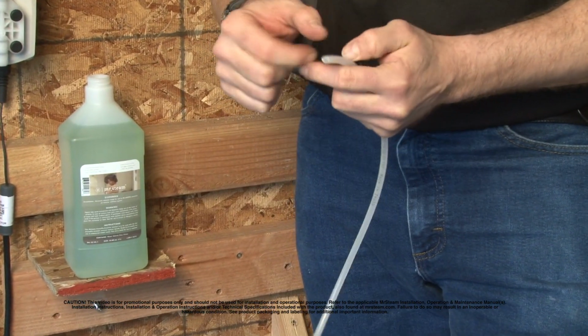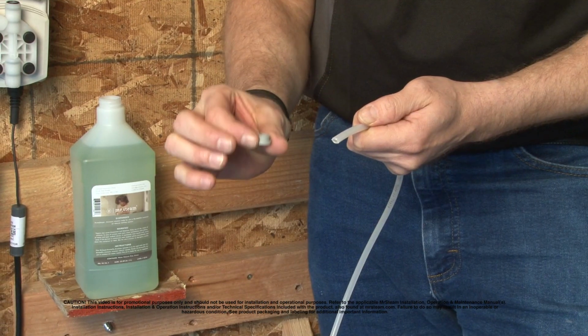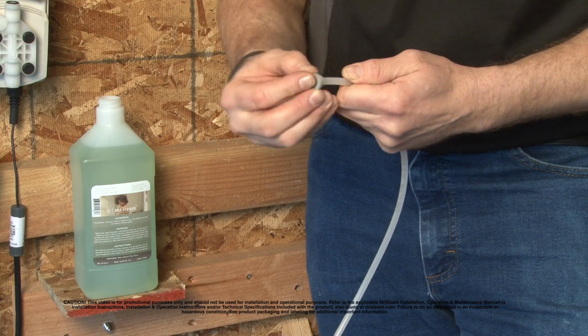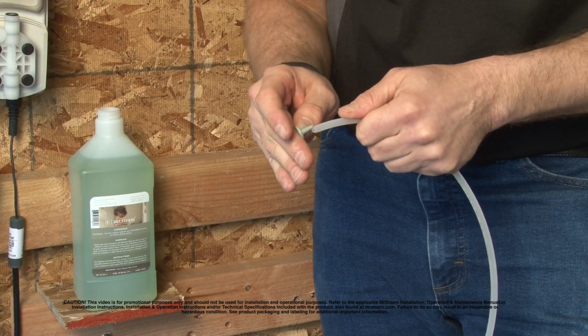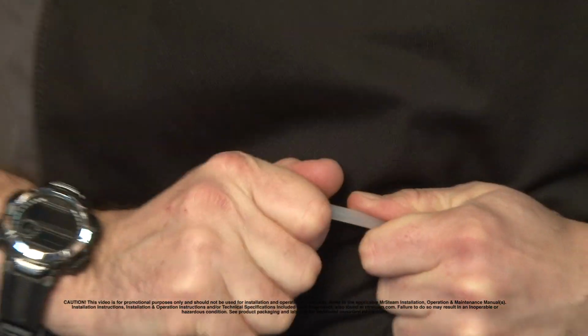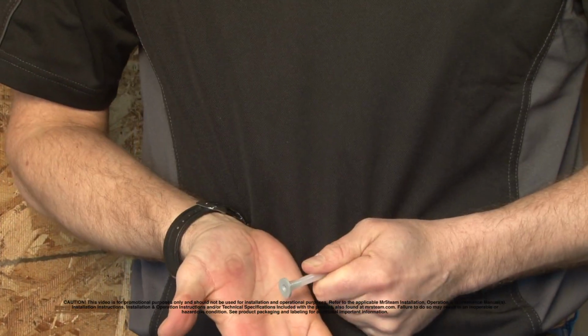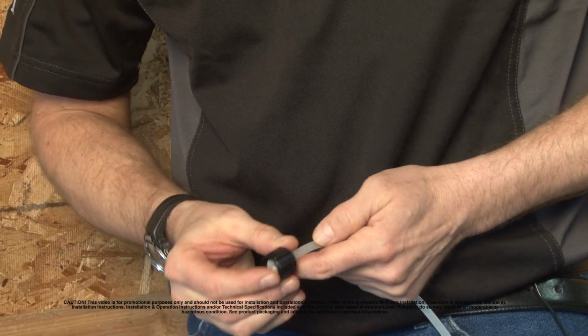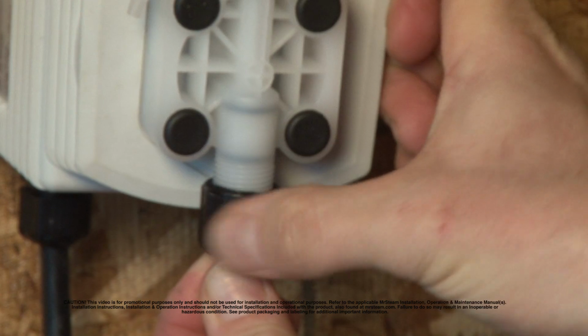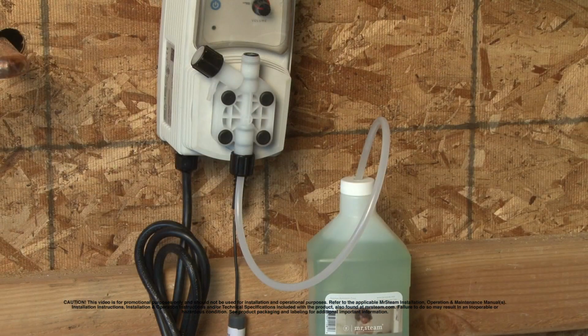Next, the other end of the hose should be threaded through this tightening nut and collar, and the tube holder nipple should be pushed all the way into the hose. Attach this hose to the pump by screwing the tightening nut onto the bottom of the pump head, like so.